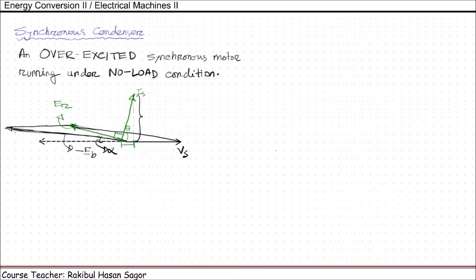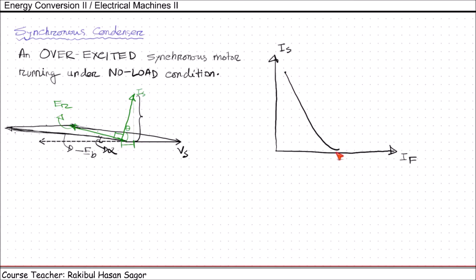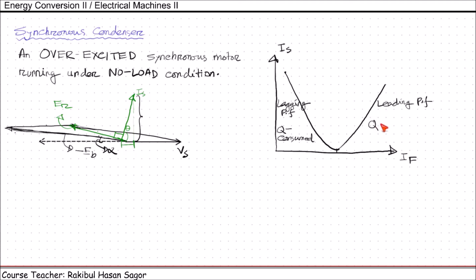If we draw the V curve for the synchronous condenser, with the x-axis where we will take field current and the y-axis where we are going to take armature current — for a certain field current it will start from here, and the armature current will go almost near to zero value, because at unity power factor the current is very very low, and again it will be increasing. The V curve looks like this. We have lagging power factor here, where Q — that means reactive power — is consumed. And this is the unity power factor case. And here we have leading power factor, and at this region reactive power is supplied to the system.